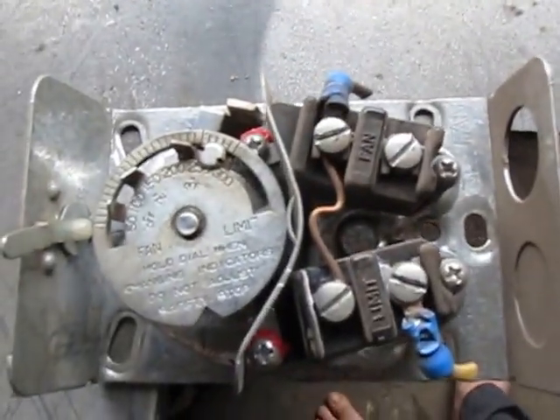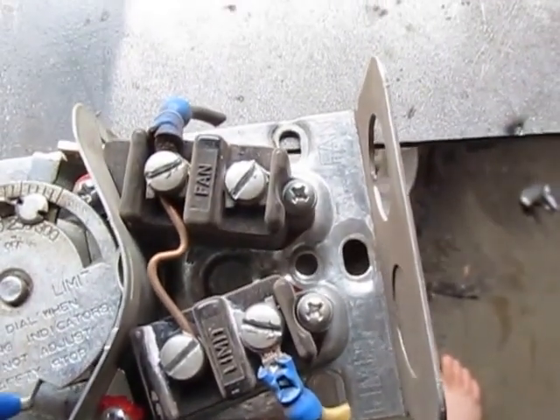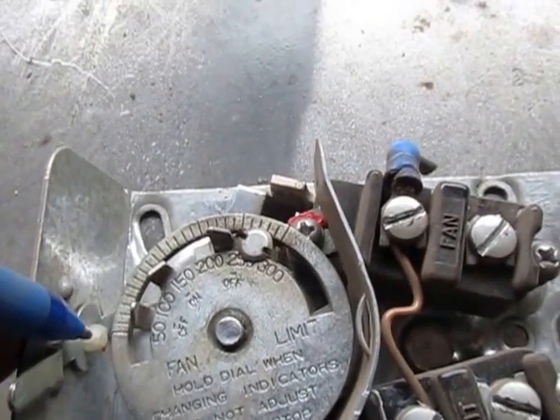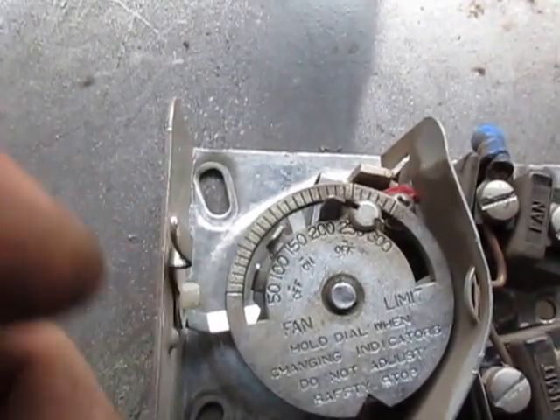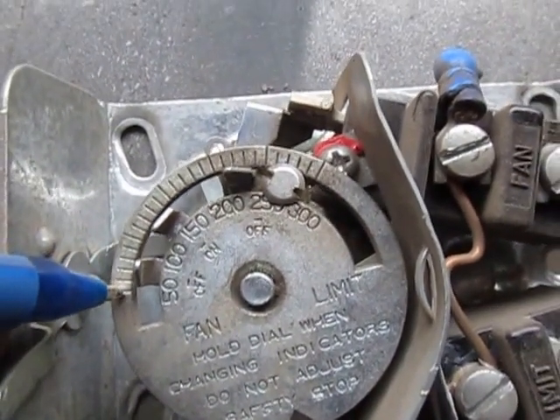That's the Honeywell fan limit control. The White Rodgers is very similar — it has a slide lever on it, manual/automatic, made by White Rodgers. Another good fan limit control; they both work very well. On this one here you have the same type of temperature clock that turns and three adjusters. Your calibration line on this one is this plastic pin where the lever pivots right here — this lever pivots back and forth, and that plastic pin is your calibration line.